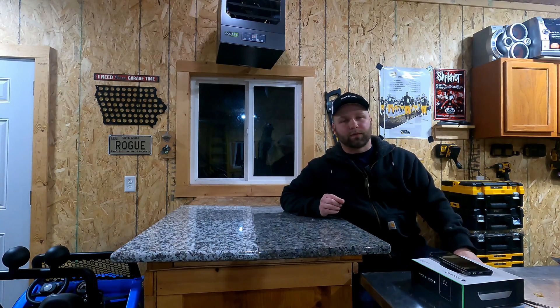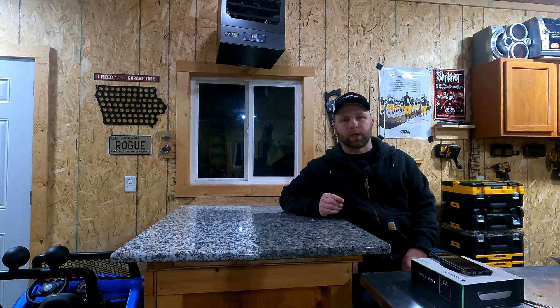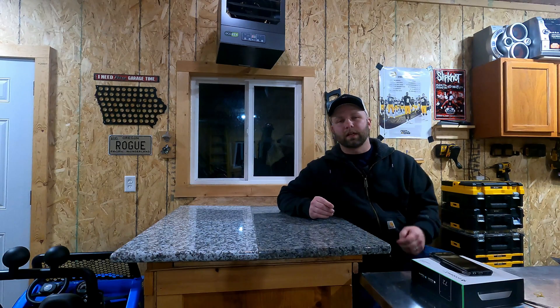The way I've got it set up, I'm trying to save as much money as possible — curious to see how cheap you can do it and keep this above freezing. It stays 45 degrees all the time regardless of how cold it is outside. This is just a hair over 25,000 BTU per hour from this 7,500-watt, 240-volt King Electric Eco 2S Plus. It does a great job — it'll take a little longer to heat up a wider range, but once it gets there, it holds it well.